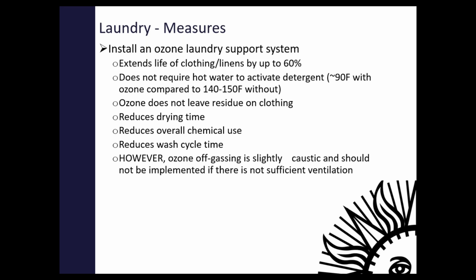The other thing that you can be claiming is the water is not required to be up to 140 or 150 to activate the detergents. So you can run it with 90-degree water, save yourself some domestic hot water heating energy there as well. I've heard claims that it does reduce drying time and chemical use, but I don't personally have experience with it, but this came directly from the CWEP class.